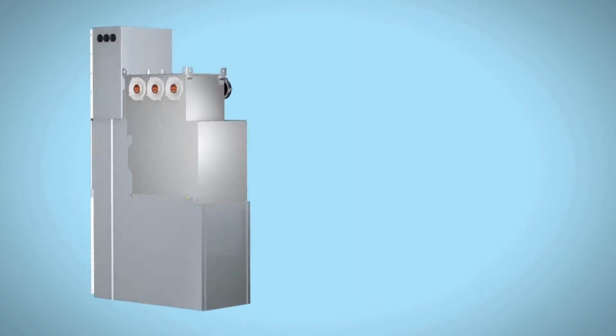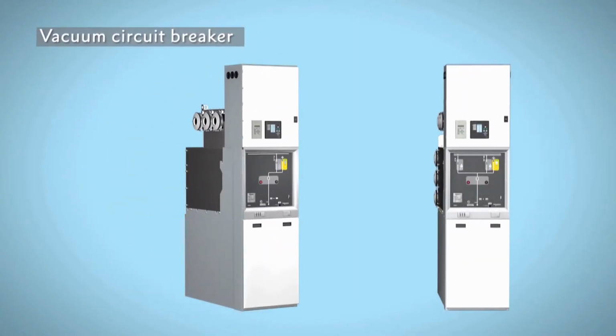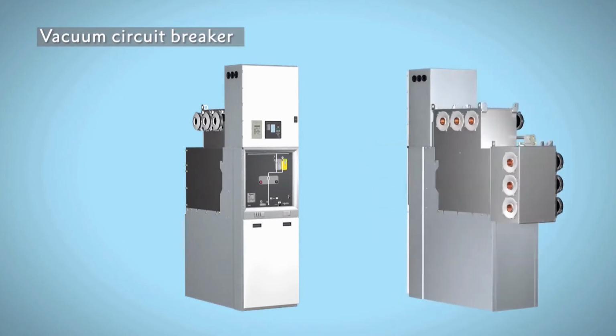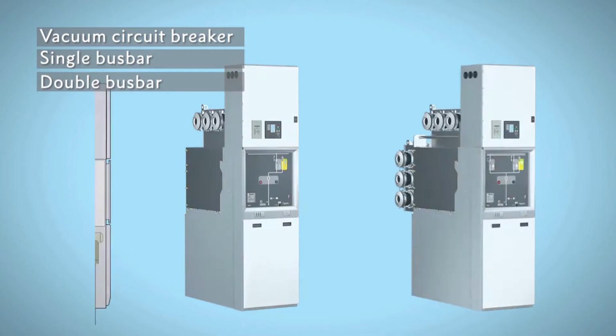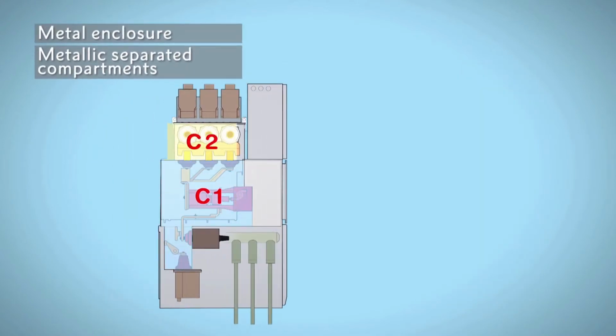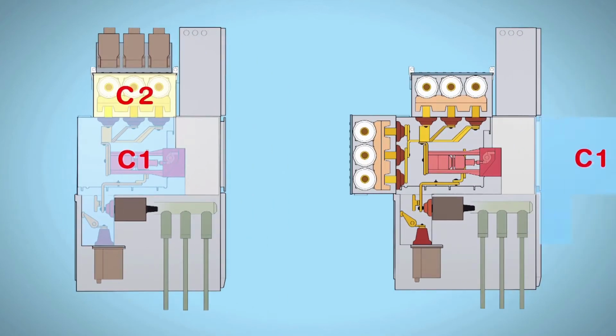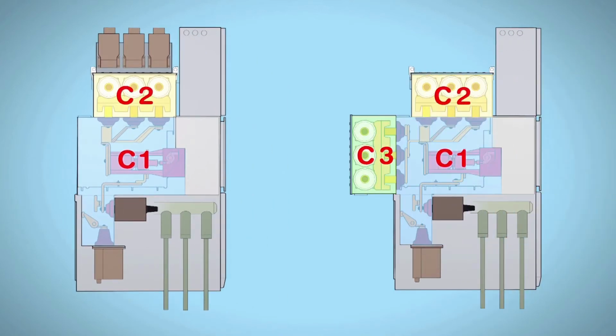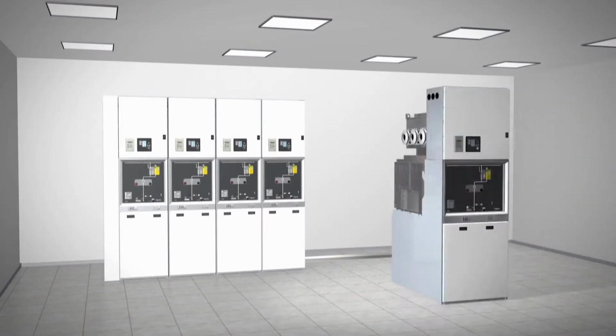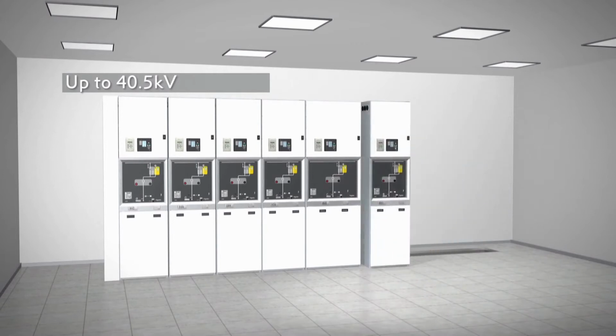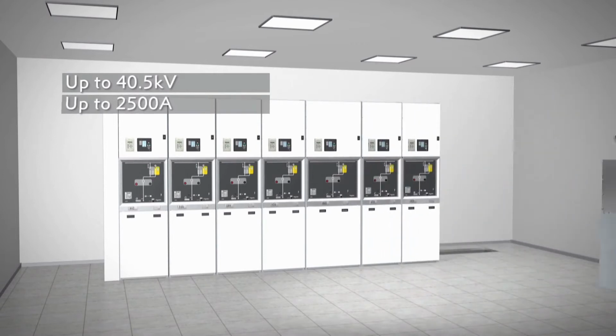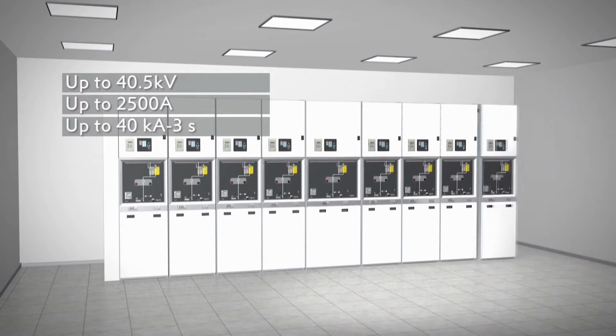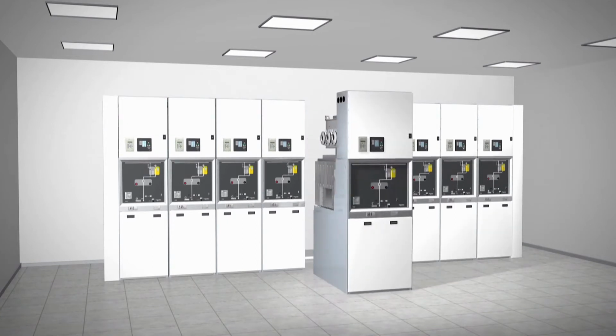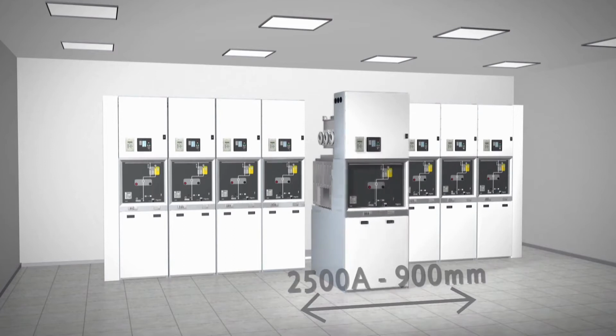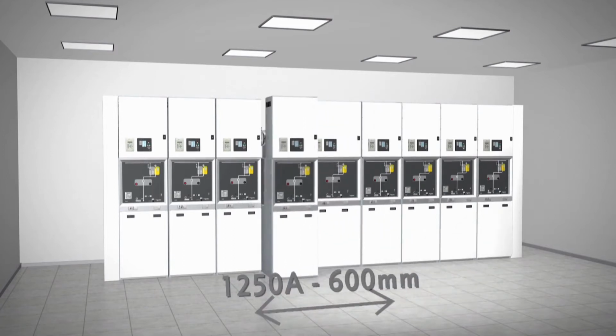GHA is indoor, metal-enclosed gas-insulated switchgear with vacuum circuit breaker technology for primary distribution, available as a single or double busbar solution. The metal enclosure and metallic compartments, separating the circuit breaker and three-position switch from the main busbar, ensure high availability. GHA is designed for 1 to 3 phase applications up to 40.5 kV, with busbar and feeder currents of up to 2,500 amps and rated short-time current up to 40 kiloamps for a duration of 3 seconds. Compact and naturally cooled, the incomer for up to 2,500 amps is 900 mm wide and typically 600 mm for feeder applications.